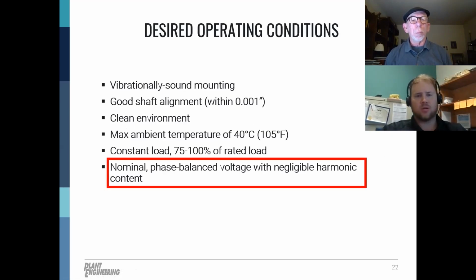So to start, let's talk about ideal operating conditions for your motors. Ideally, you would be getting nominal balanced voltage from your power utility. So for instance, what does that mean? If you have a 3-phase 480 volt supply, those phases may be balanced to within 1% or better. That's ideal. But the more out of balance, the more detrimental to the motor's efficiency and long-term reliability.